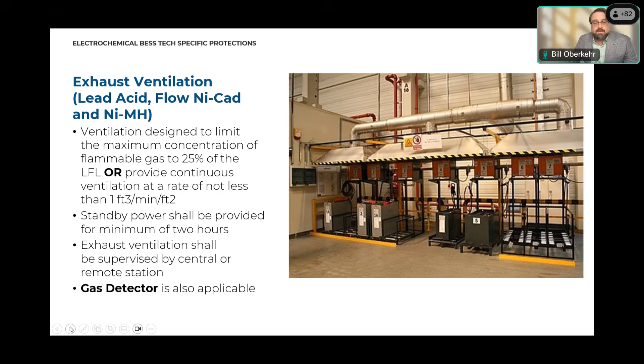Exhaust ventilation is not required for lithium ion because during normal charging and discharging operations we are not seeing toxic gases. That is not true for lead acid batteries, flow batteries, or nickel cadmium, so exhaust ventilation is required for those systems.